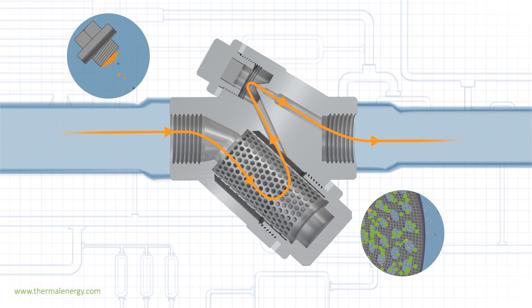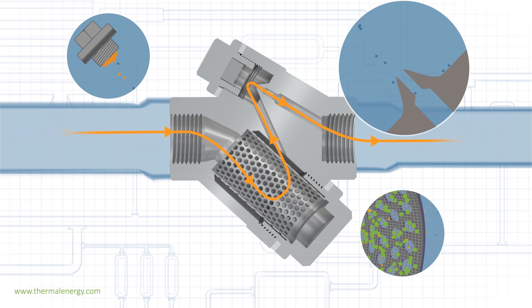All our low-duty traps are designed with inverted cone technology, as a final barrier against blockage. This feature deflects micro-debris away from the orifice, or breaks up smaller particles which have become stuck together, allowing them to pass through the orifice without concern. The inverted cone was first developed and patented by Thermal Energy. As the original creators of this feature, we worked with one of the world's foremost tire manufacturers to overcome the challenge of grease and rubber particles in its system.